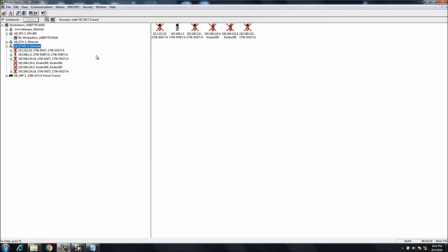I understand that it's easy to be able to use Ethernet and look at these drives, but again, this is a SERCOS drive. This is a Kinetix drive. This is not a CIP Motion drive. This actually talks through SERCOS. Now being that you can see it, you think you would be able to get online with it just like that.